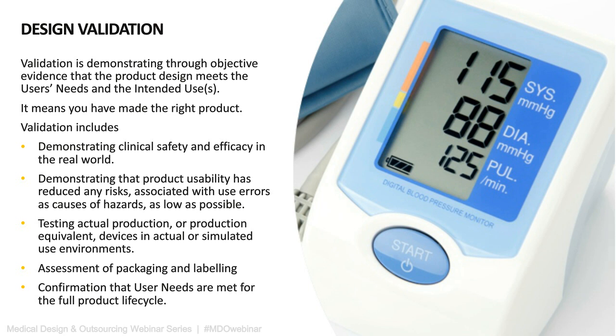Too often we see people do some early evaluations in the clinical setting with a prototype, and then they try to bring that over and say, okay, well, this issue was all handled early, but the final product actually might have a different user interface which negates that earlier work. And so you really need to test your production or production equivalent products in that final evaluation. And validation also should include the assessment of packaging and labeling. So it's not just does the product work, does the instruction manual work? Does the product safely get to the client to where it's not damaged?